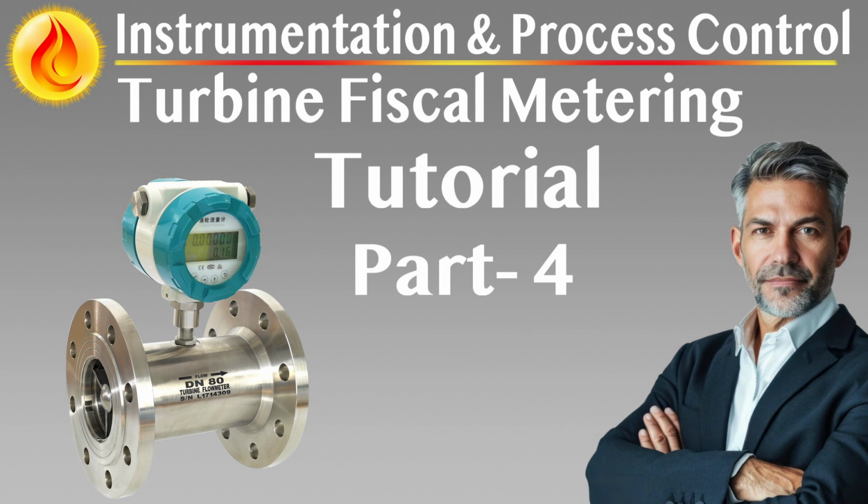durability. For bidirectional provers, a 4-way flow diverter valve must be installed to reverse the direction of the fluid and the sphere. This valve must operate with minimal turbulence or pressure disruption and maintain tight sealing to avoid volume leakage or bypass during the proving run. The valve's position must be monitored continuously, with leakage alarms tied into the prover control system.